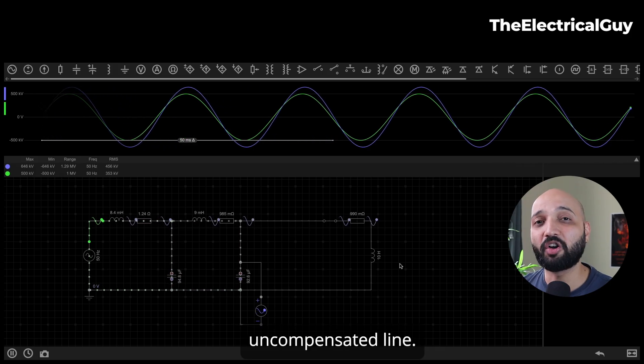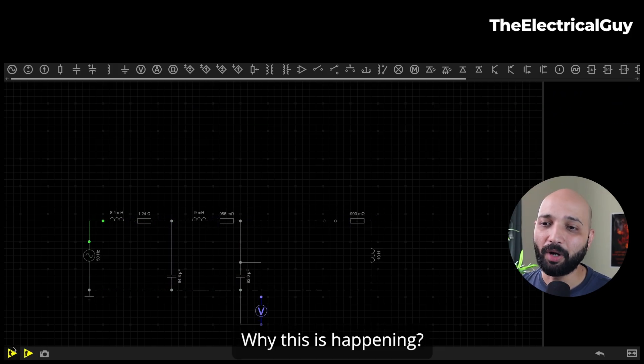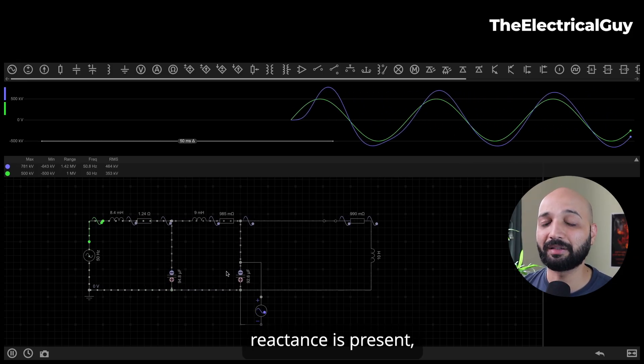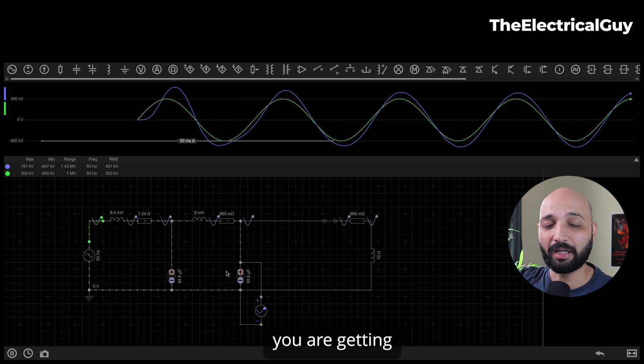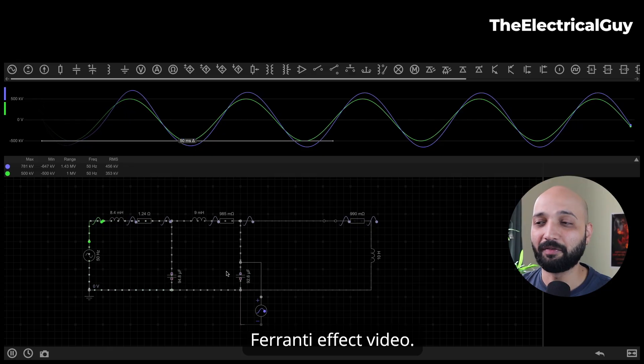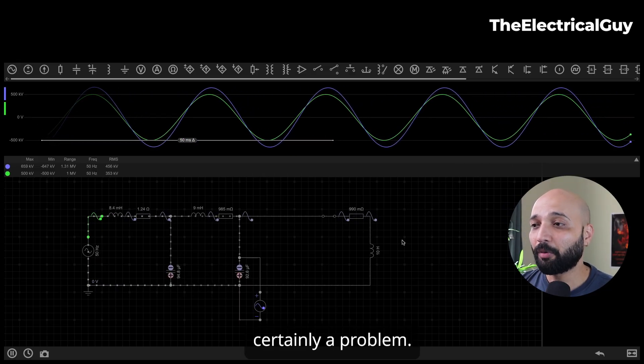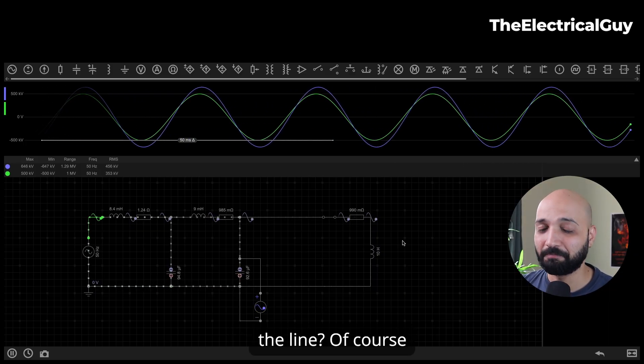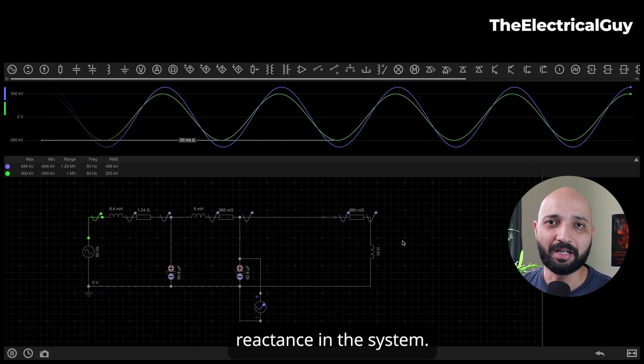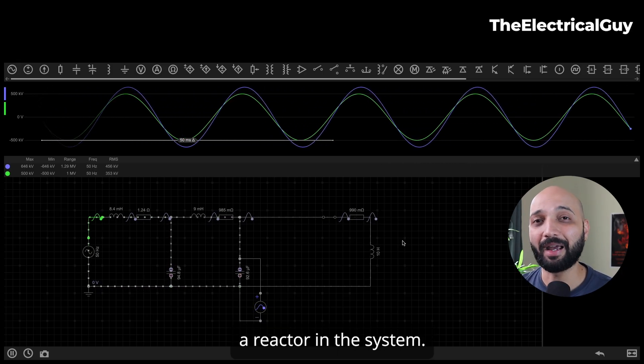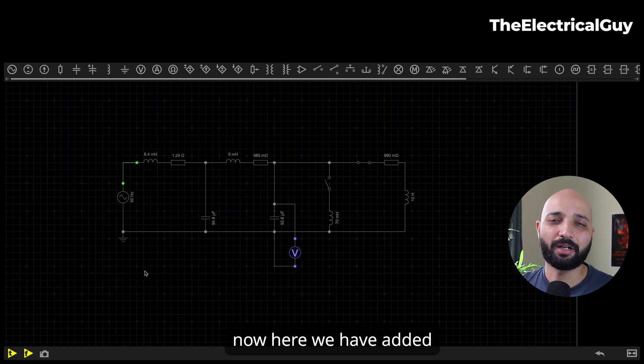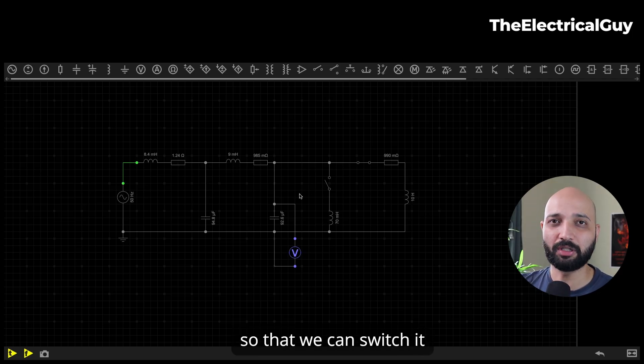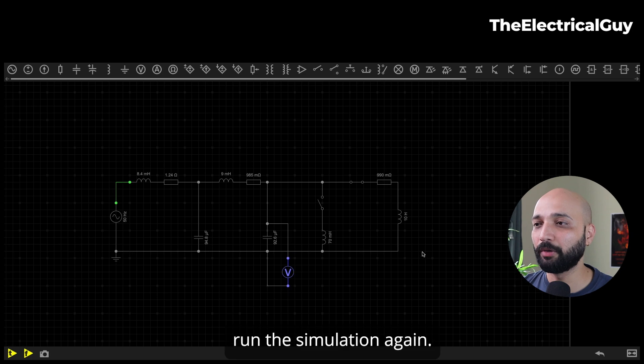This is what we call an uncompensated line. It happens because there is no sufficient inductive reactance in the system — the capacitive reactance is dominating, giving high voltage at the receiving end, which is the Ferranti effect. To address this we compensate the line by adding sufficient inductive reactance. So let me go and add a reactor to the system — you can see the reactor has been added along with a switch so we can switch it when needed.